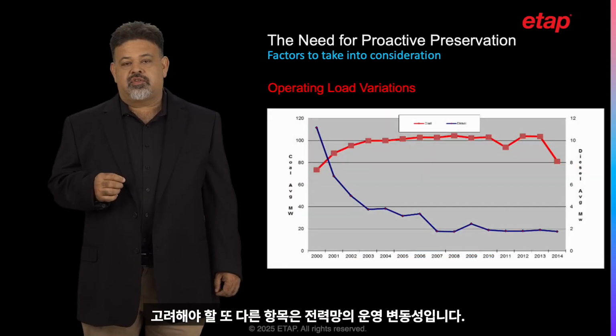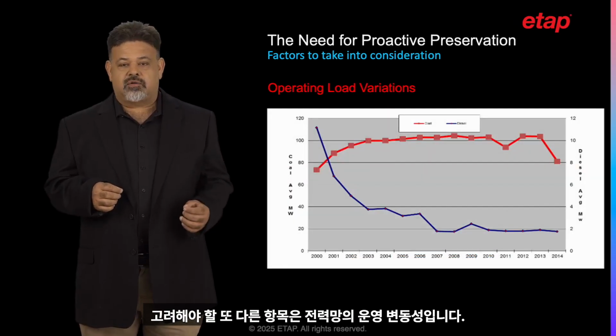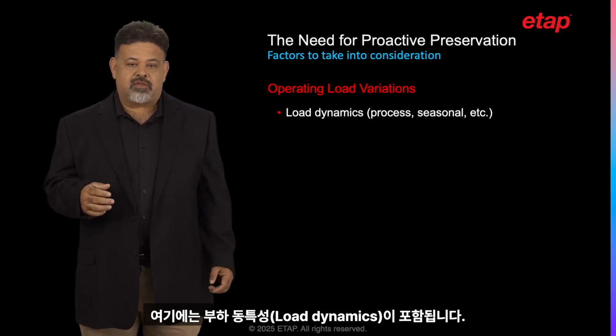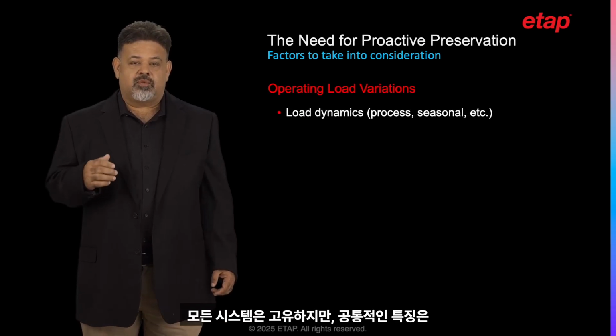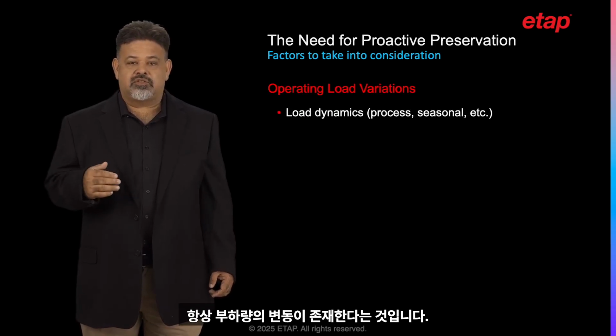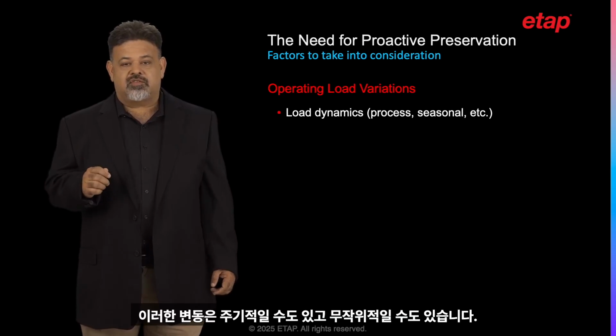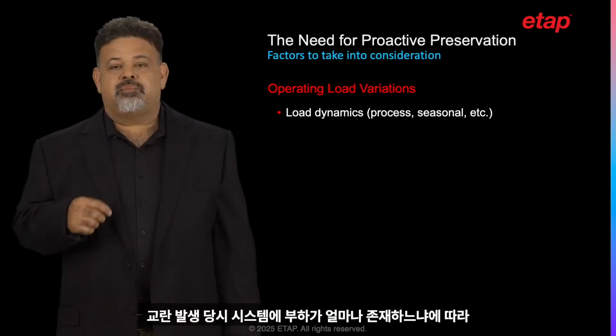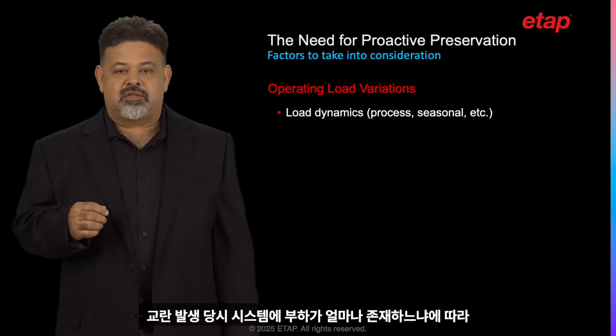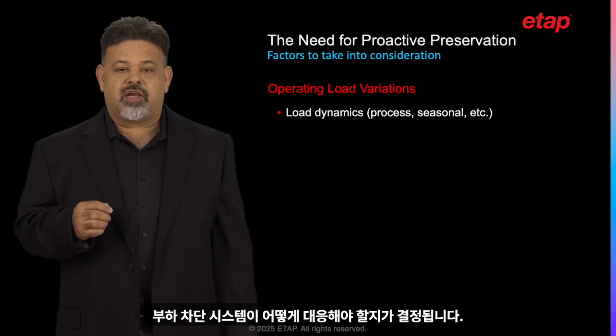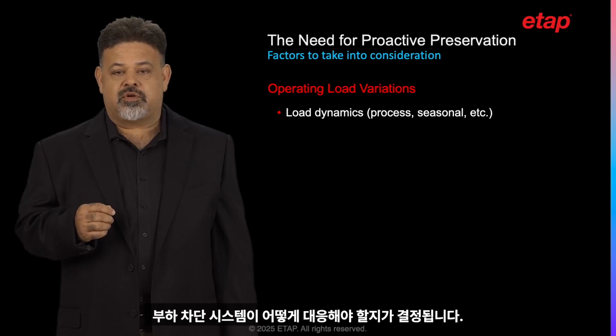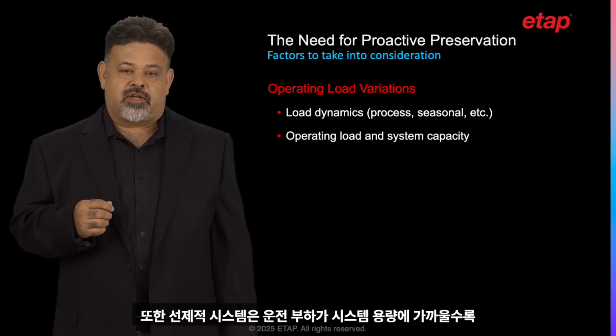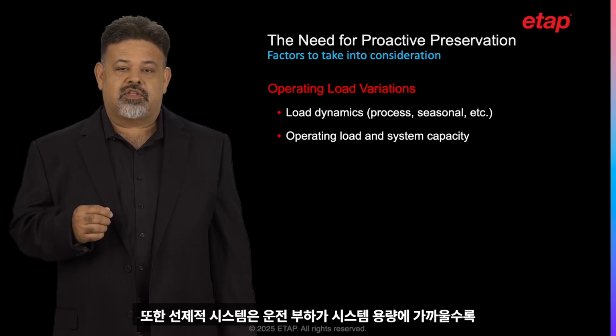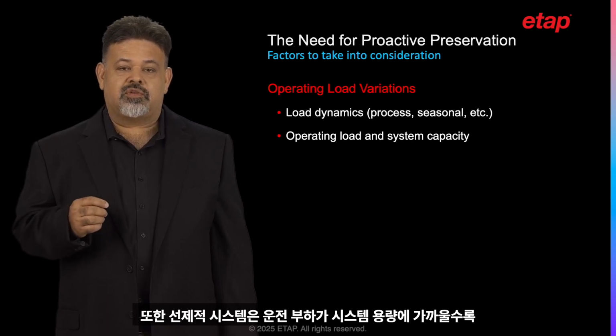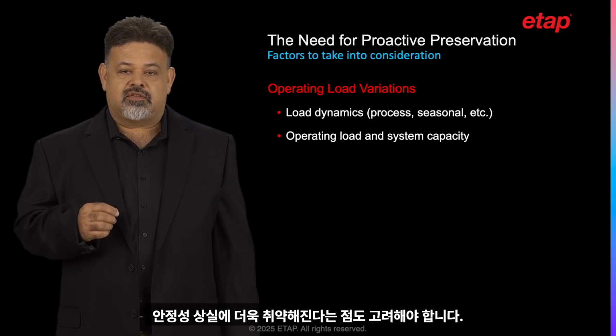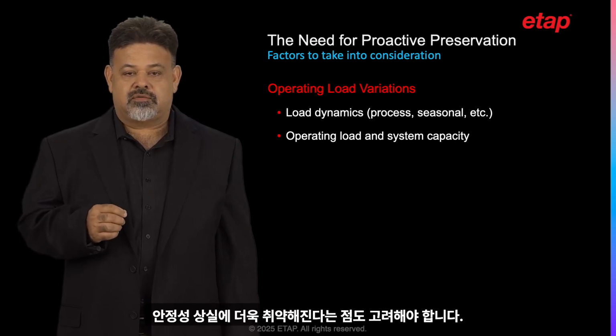One other item to consider is the operation variations in the electrical network. This includes the load dynamics. Every system is unique, but what is common with all systems is the variation of loading. Sometimes it can be cyclic or it can be random. How much load there is in the system at the time of the disturbance will determine how the load shedding system will need to respond. The proactive system must also consider that if the operating load is closer to the capacity, the system is more susceptible to stability loss.